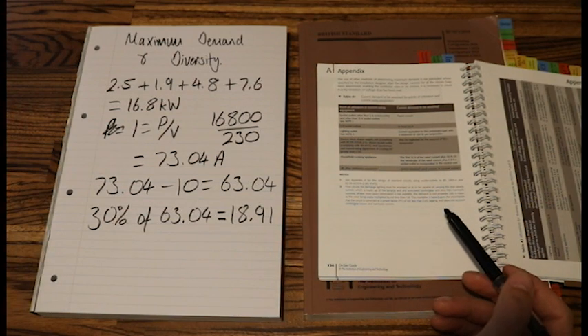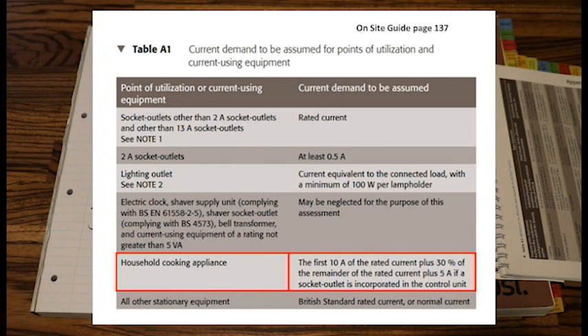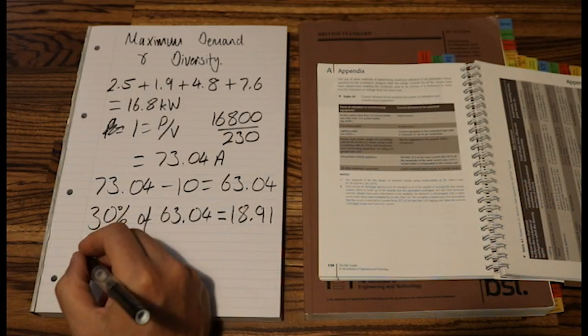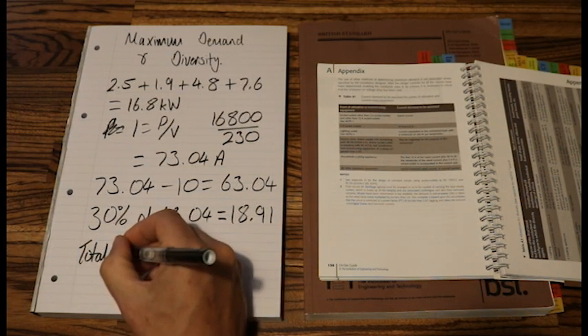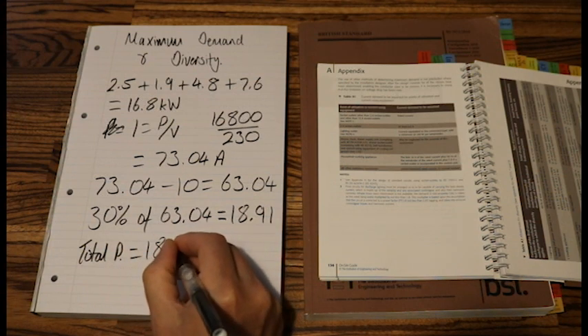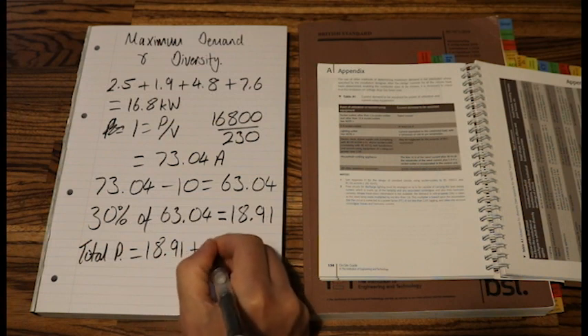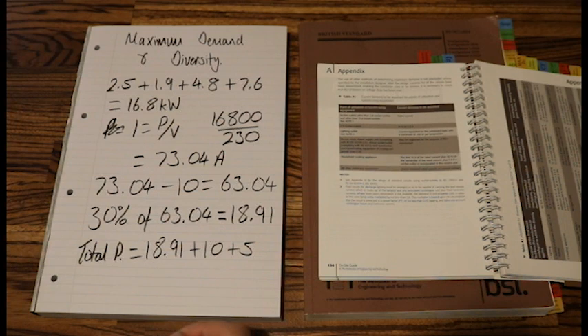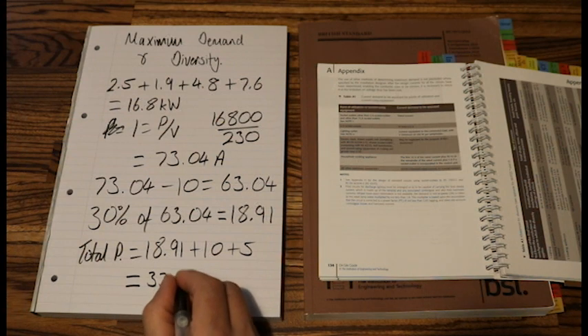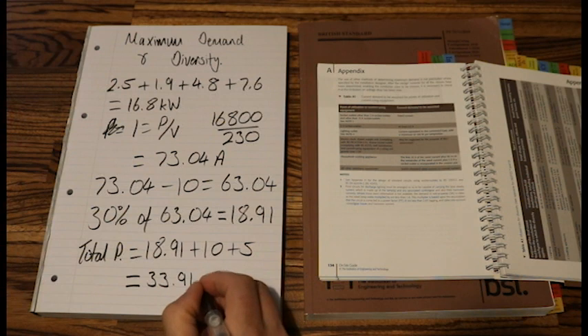And then we add the first 10 amps we took off to this 30% of the remainder. And the table A1 also says that if a socket outlet is incorporated into the control unit, we add an additional 5 amps. So my total current equals, let's add them all together. So we've got 18.91, plus 10, plus 5, and that equals 33.91 amps.